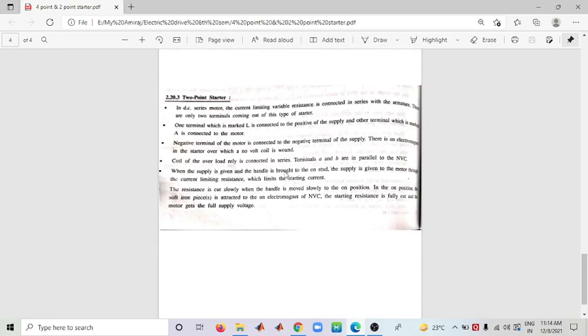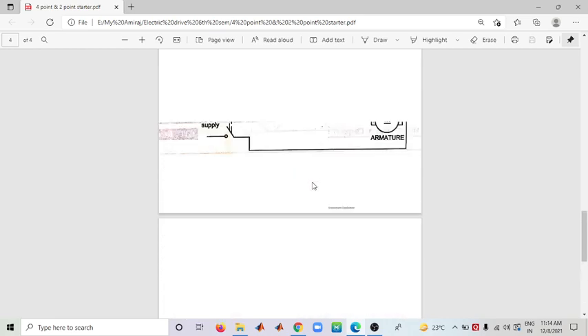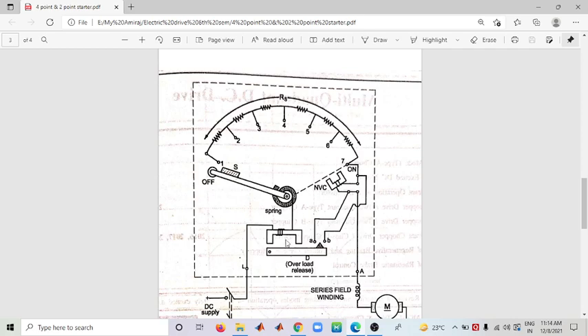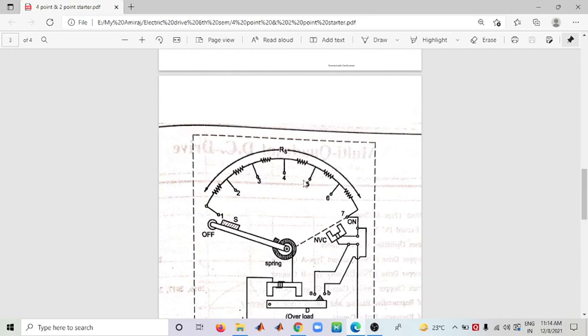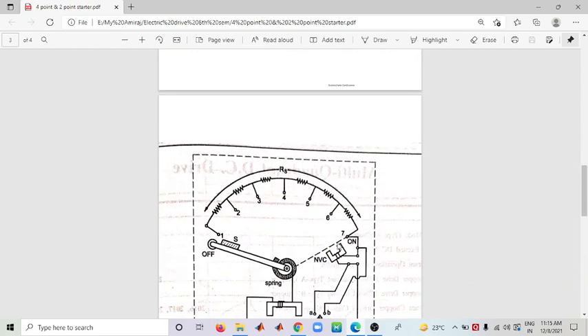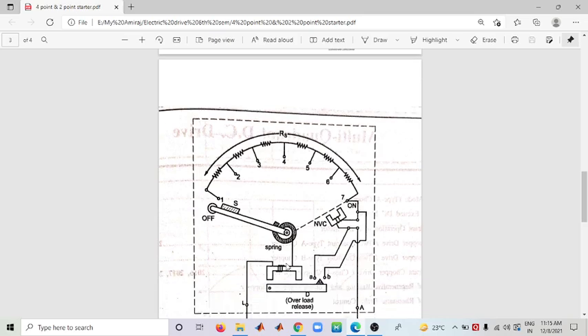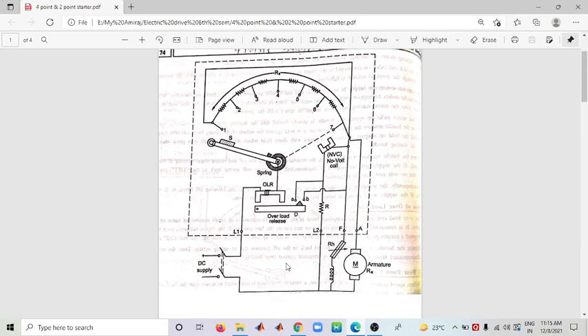When supply is given to the handle in the ON position, the supply is given to the motor through the current limiting starting resistance. As the handle is moved slowly to the ON position, the resistance is cut one by one. A soft iron piece is attracted by the electromagnetic energy. When the starting resistance is fully cut, the motor gets the full supply voltage.